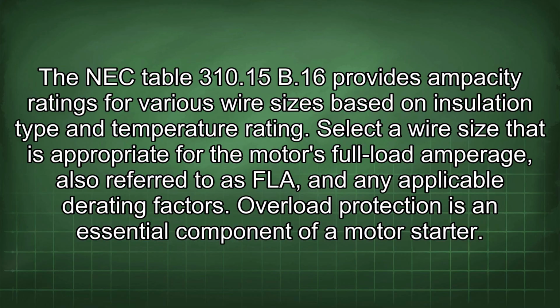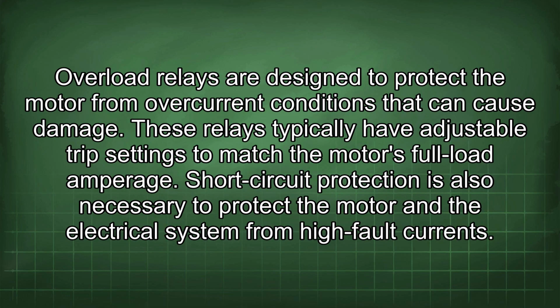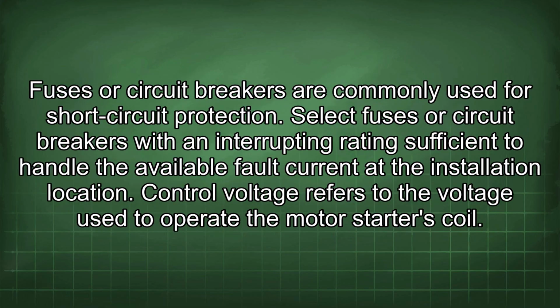Overload protection is an essential component of a motor starter. Overload relays are designed to protect the motor from overcurrent conditions that can cause damage. These relays typically have adjustable trip settings to match the motor's full load amperage. Short circuit protection is also necessary to protect the motor and the electrical system from high fault currents. Fuses or circuit breakers are commonly used for short circuit protection. Select fuses or circuit breakers with an interrupting rating sufficient to handle the available fault current at the installation location.